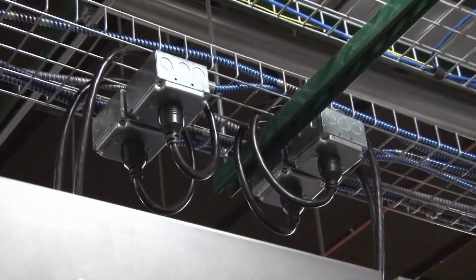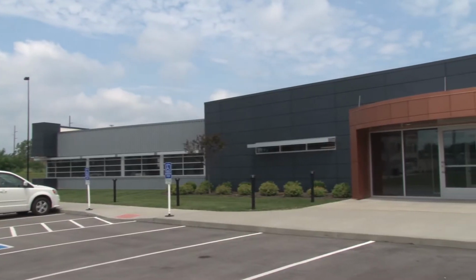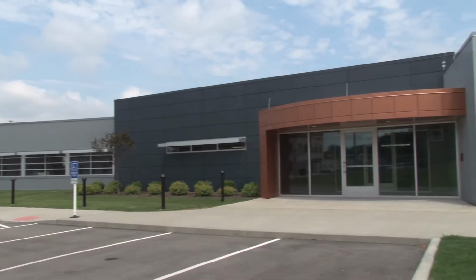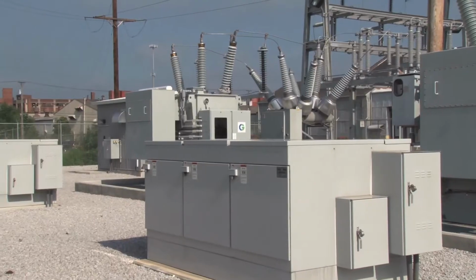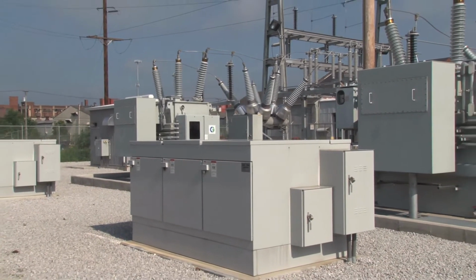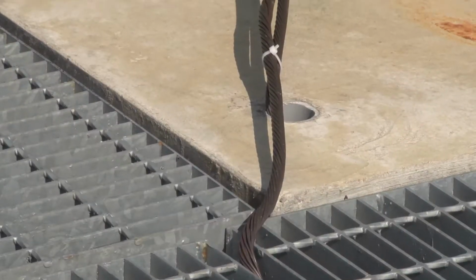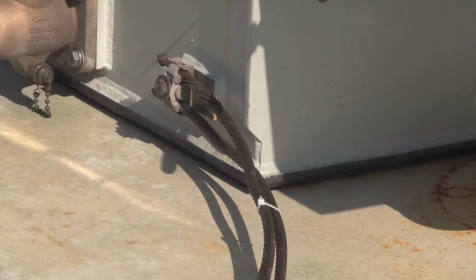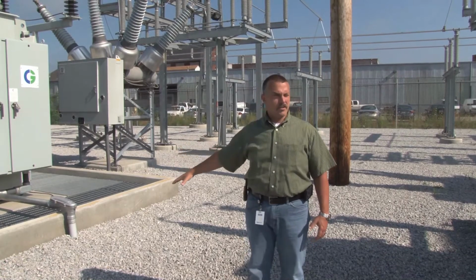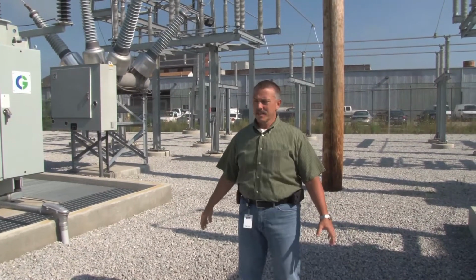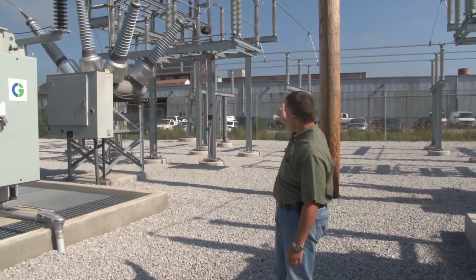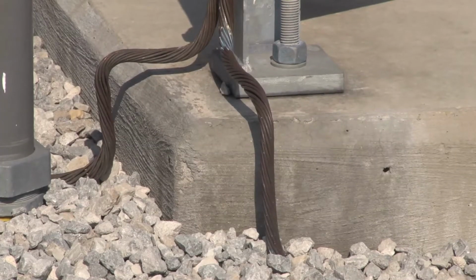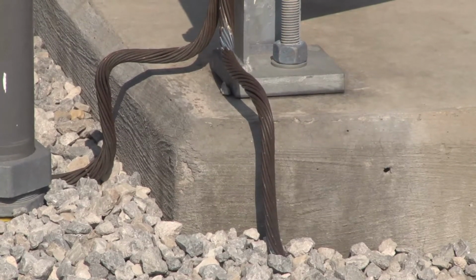Involta utilizes copper distribution to all of its data centers. We use copper from the switchgear on down. The Involta Akron data center facility is 26,400 square feet. The substation takes in 13.8 kV of power. Grounding, as you see on the transformers, goes down, and that goes down to tie into the ground grid that we have buried below the subyard. You'll also see in the background that we have that coming off the columns that support the busway areas for all the power distribution coming in.